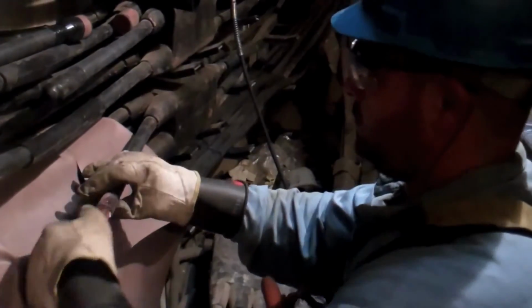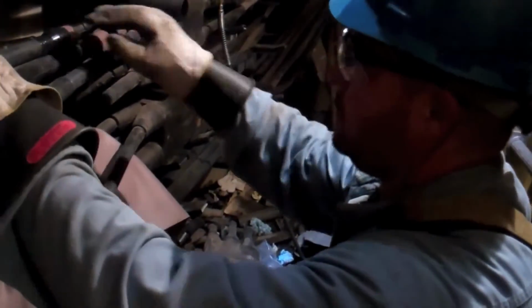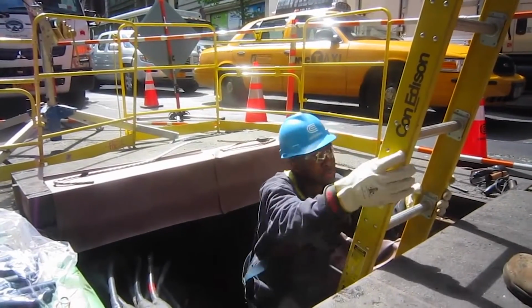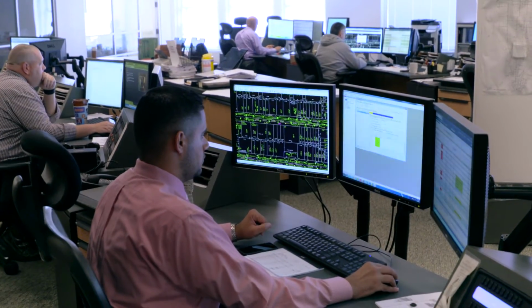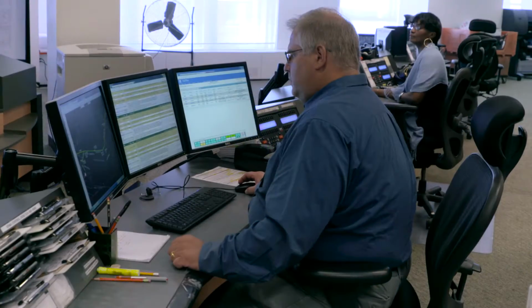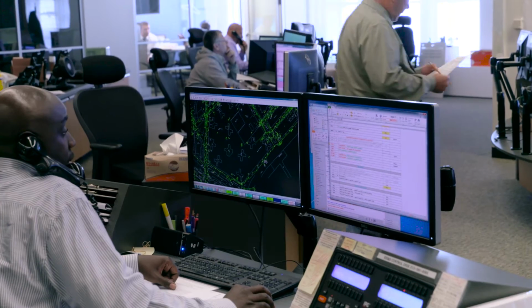Con Edison was able to come up with a smart grid program that allows them to implement a SCADA system to measure the consumption of the building versus the output of the solar system. This lets the transformer accept some amount of backfeed before it starts shutting off voltage to the building. We were comfortable as engineers that we weren't compromising the reliability of the grid.